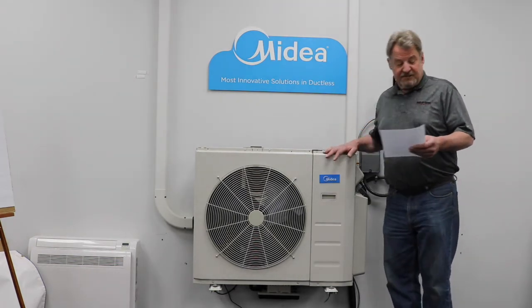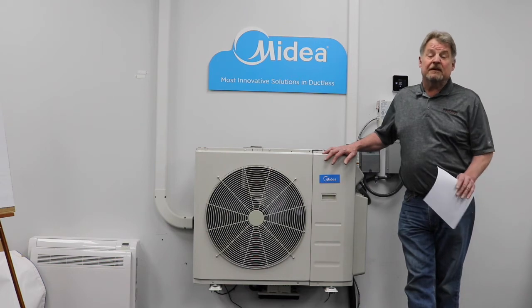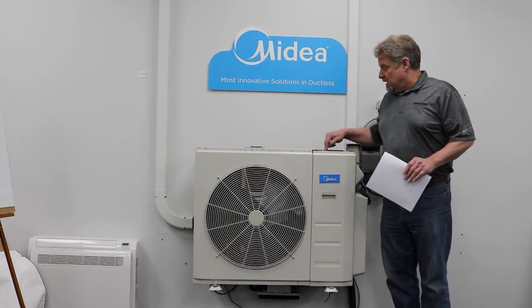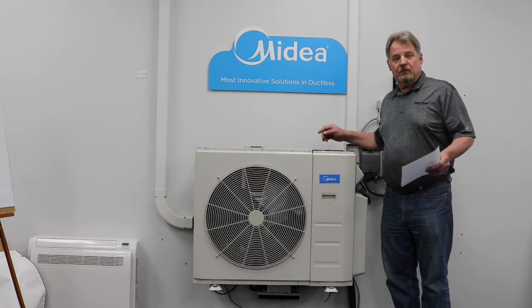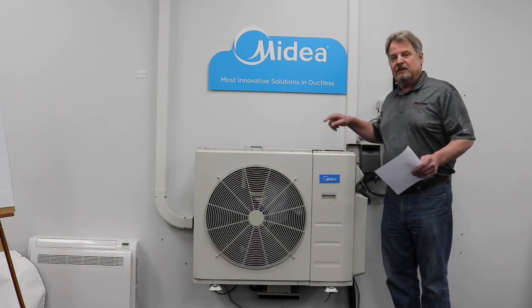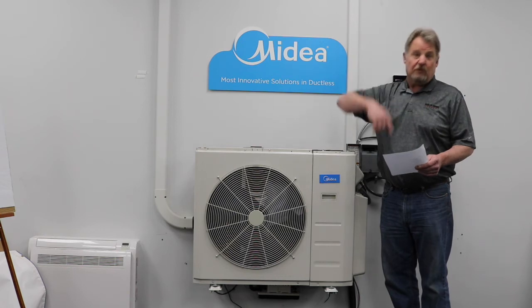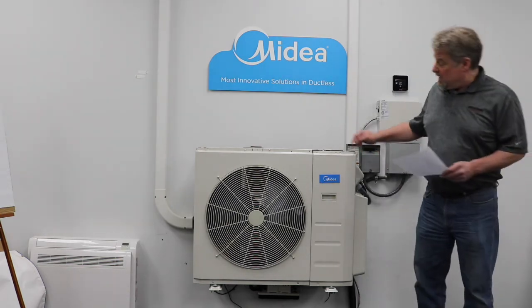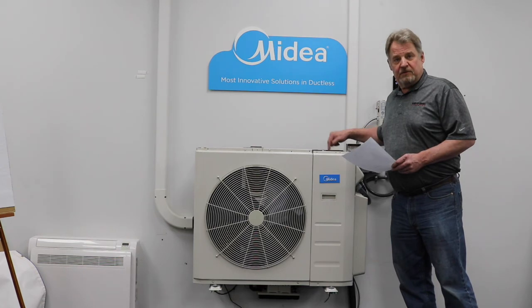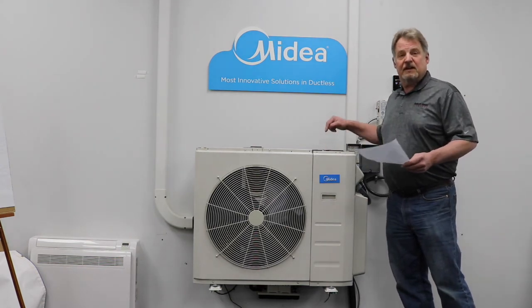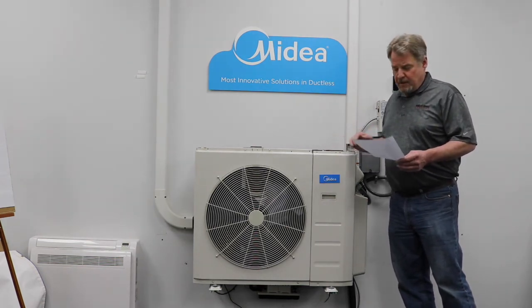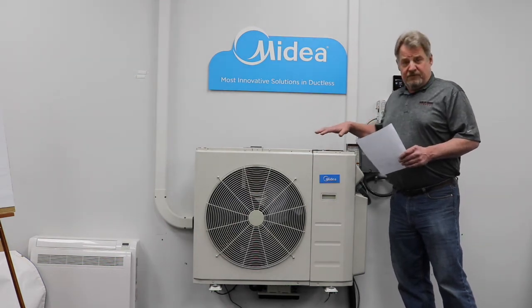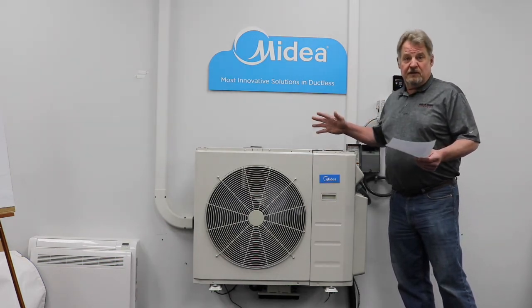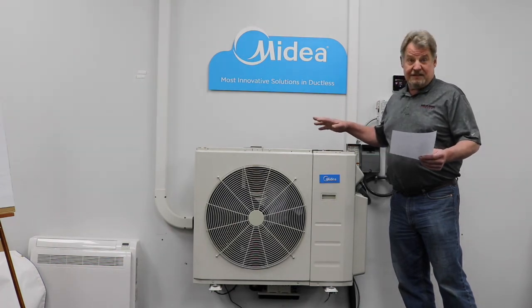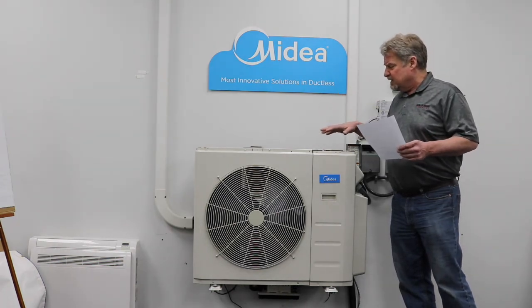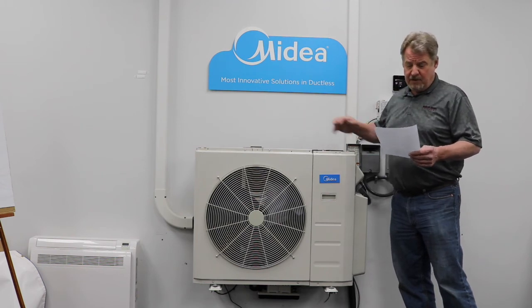Like I said, we go from number 1 to number 51. If I continue quick enough, I can go 1, read, press the button to 2, and it will continue on, so I don't have to scroll through the whole number. It's also going to keep track, as I'm pressing the button, of what number I've pressed. So if I have to go to number 47, it'll go 1, 2, 3, all the way up to 47. So this is a troubleshooting feature on the multi-zones, which is really tremendously helpful. I've used it a lot in troubleshooting these, plus again the fault code actually shows up on here.